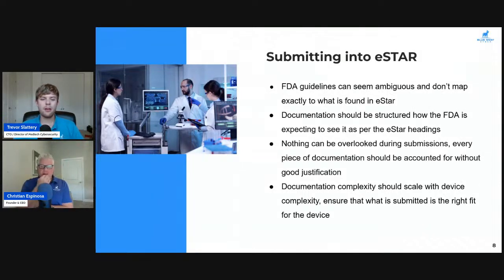Now, finally, documentation complexity should scale with the device complexity. If a device is very simple, it only does one thing, and it's a pretty low risk, it's likely the documentation is going to reflect that. There won't be a ton of documentation on cybersecurity controls, and the cybersecurity testing will be fairly brief, as there just isn't too much to test and there isn't too much to implement controls around. Inversely, large, complex systems with many interconnected components operating in a very dangerous environment are going to have a lot of different documentation requirements to ensure that it's being addressed safely.